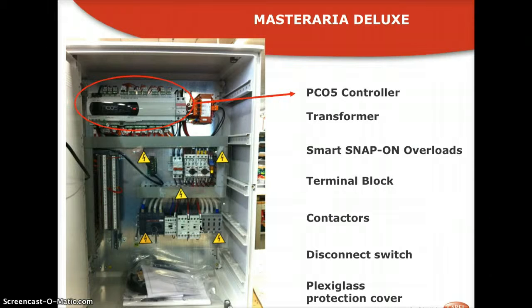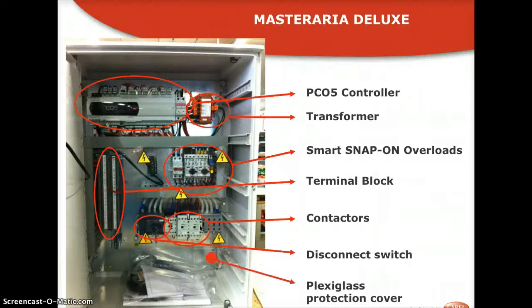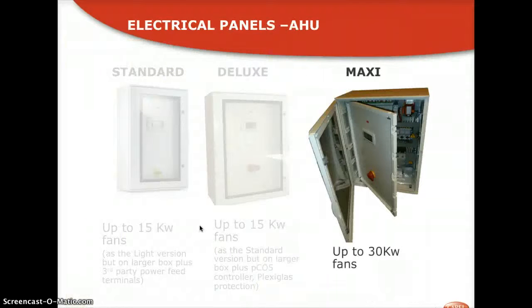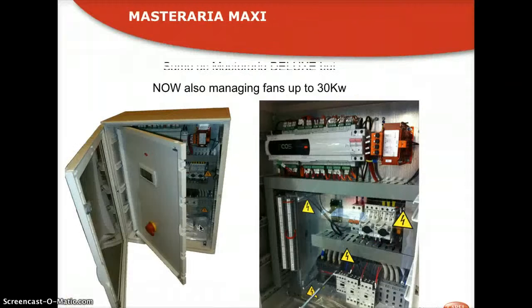So you can see the PCO5 controller, the transformer. Here you have the MCB overloads and the contactors. The disconnect switch is always in the center of the panel, and here on the left you have the disconnect switch, the terminal blocks, and this is the plexiglass protection cover. The Masteraria Maxi instead has got the same identical construction and components of the Masteraria Deluxe. However, the contactors and the MCB overloads are rated for motors up to 30 kilowatts.